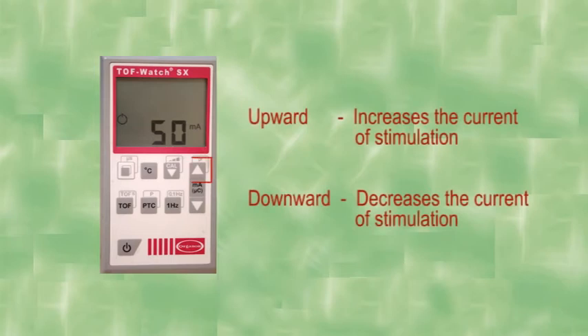We come to the next button. This is the button which shows MA, which is milliamps, or micro C, which is microcoulombs. This button has an upward arrow and downward arrow. Pressing this button upward results in increasing the milliamperes and it delivers more current. Decreasing, on the other hand, decreases the amount of current delivered. Yet another function of the same set of buttons is that when they are pressed simultaneously together, a menu opens which can be used to set the calibration. This is not routinely required, however, it is better to be aware of this function.